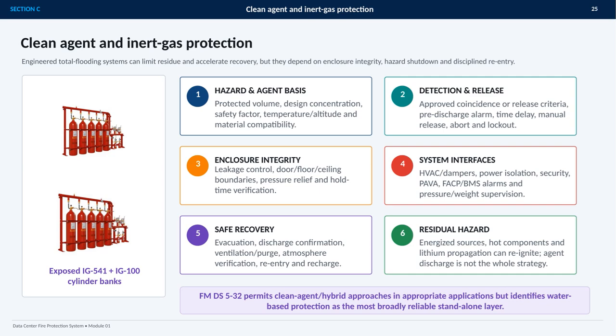First, the hazard and agent basis must account for protected volume, design concentration, safety factors, temperature, altitude, and material compatibility. Detection and release controls then need approved coincidence or release criteria, pre-discharge alarms, time delays, manual release, abort functions, and lockout provisions. Enclosure integrity is equally important. Doors, floors, ceilings, leakage control, pressure relief, and hold time verification determine whether the agent can remain effective.